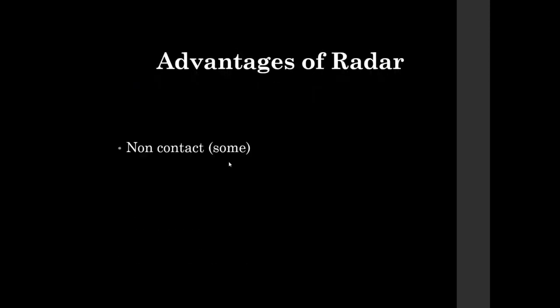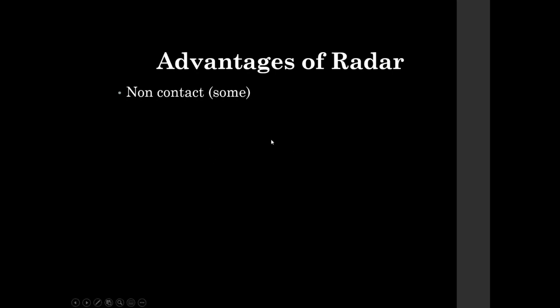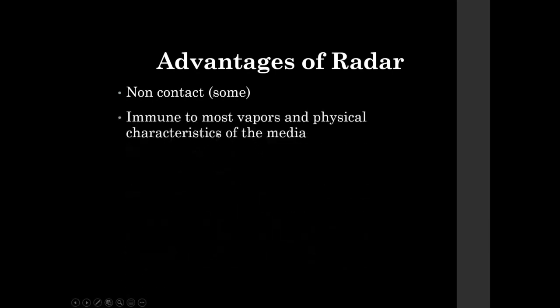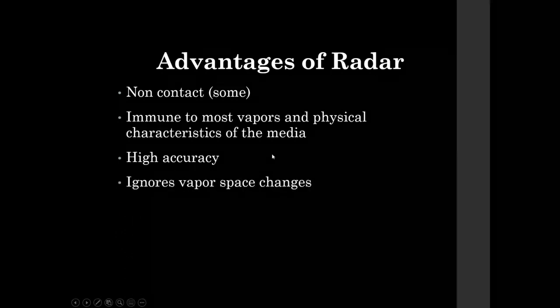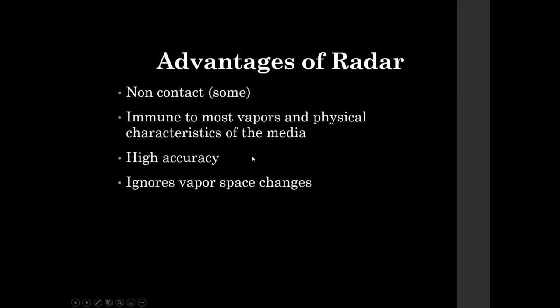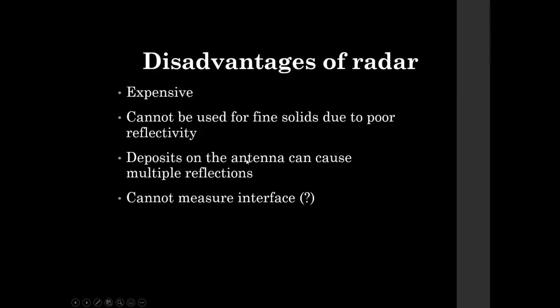Okay, advantages of radar. At least when we start out here, they're non-contact. We'll spend some time talking about a whole bunch of contacting ones, but some of them are non-contacting, just like ultrasonic was. They are immune to most vapors and physical characteristics of the media, so that makes them a little bit better than ultrasonic. They're highly accurate. They're not too worried about vapor space changes, so again, problematic for ultrasonic, but better for radar.